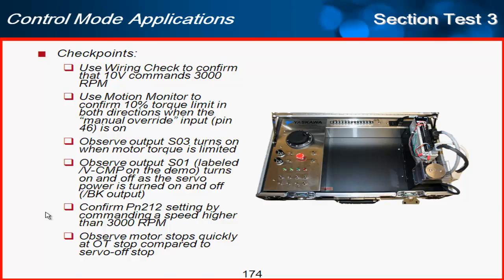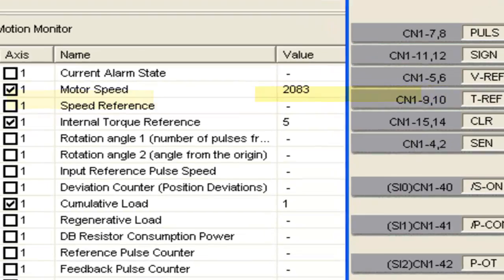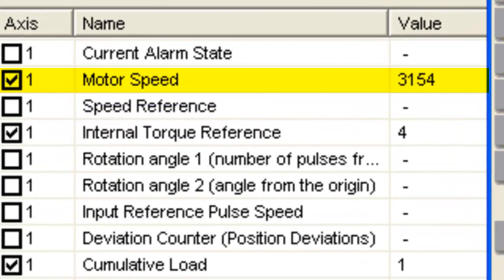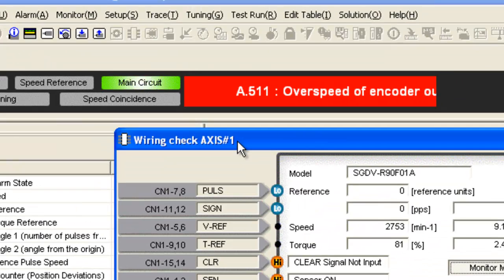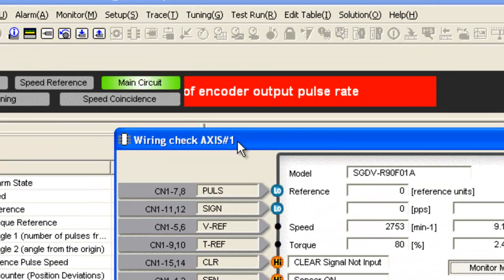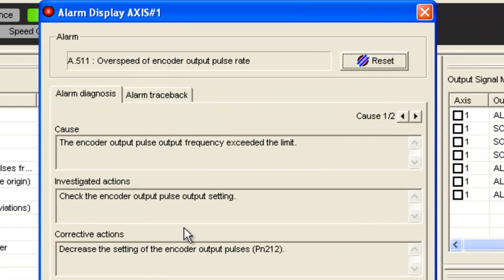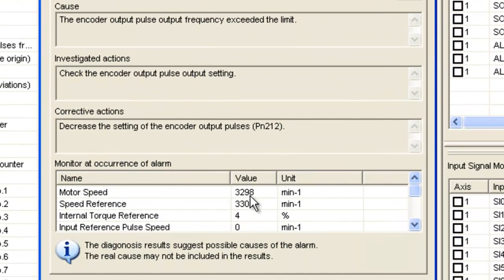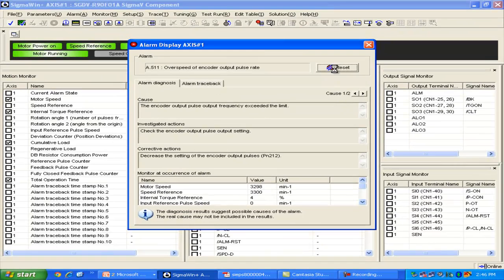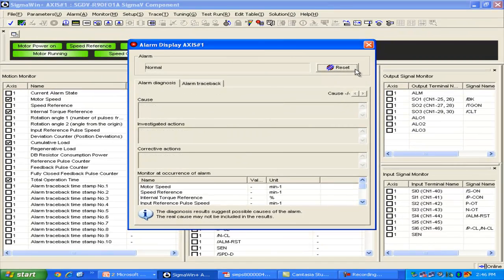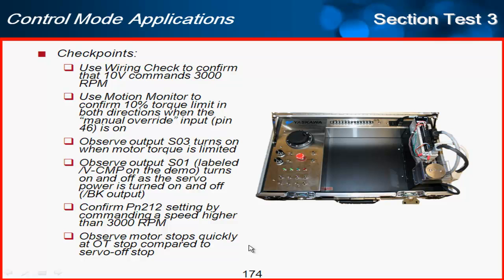Next, I'll confirm PN212 by setting the command speed higher than 3,000 rpm. Looking at the wiring check, we get an 'overspeed of encoder output pulse rate' alarm because we went too fast. Looking at the alarm detail, the motor was going 3,298 rpm — our maximum was set at 3,000. This shows how the setting relates to PN212, the output resolution. I can turn the speed back down and reset the alarm.